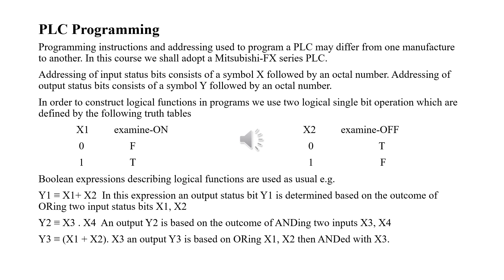Programming instructions and addressing schemes used in PLCs depend on the manufacturer and can differ between manufacturers. In this course, we will adopt the Mitsubishi FX series PLC. Addressing of input status bits in the Mitsubishi FX series is based on the symbol X followed by an octal number, and addressing of output status bits is based on the symbol Y followed by an octal number.